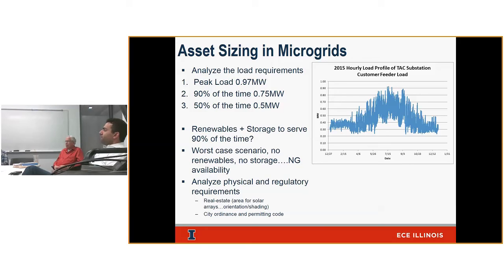So this circuit is summer peaking, with a peak of 0.97 megawatts. Really, what we want to plan for is supporting a 1 megawatt load - that's the number one goal at peak. Then we look at other scenarios for the circuit, trying to figure out the load distribution over time. 90% of the time, this circuit load is about 0.75 megawatts, three-quarters of a megawatt. 50% of the time, the load is about half a megawatt or less.